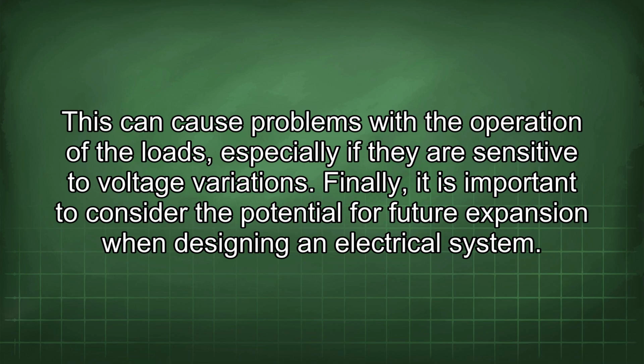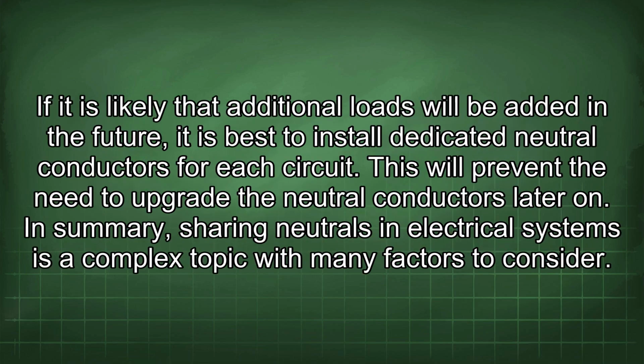Finally, it is important to consider the potential for future expansion when designing an electrical system. If it is likely that additional loads will be added in the future, it is best to install dedicated neutral conductors for each circuit. This will prevent the need to upgrade the neutral conductors later on.